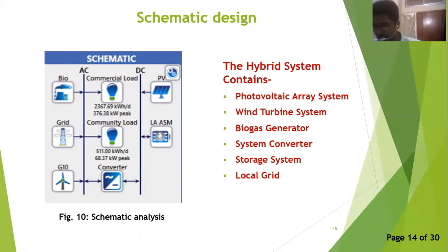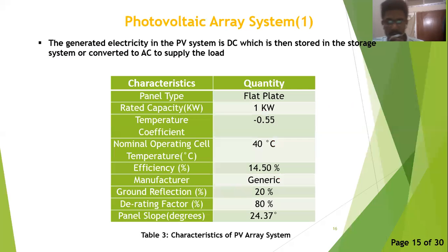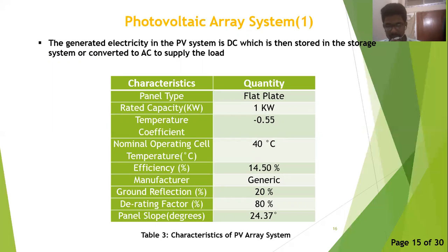The schematic design of the hybrid system is applied in the HOMER simulation software. The hybrid system contains a photovoltaic array system, wind turbine system, biogas generator, system converter, storage system, and a local grid. The PV model used in the system is a flat plate with a rated capacity of 1 kW, nominal operating cell temperature of 40 degrees Celsius, a derating factor of 80%, and an efficiency of 14.50%. Other characteristics are shown in table 3.